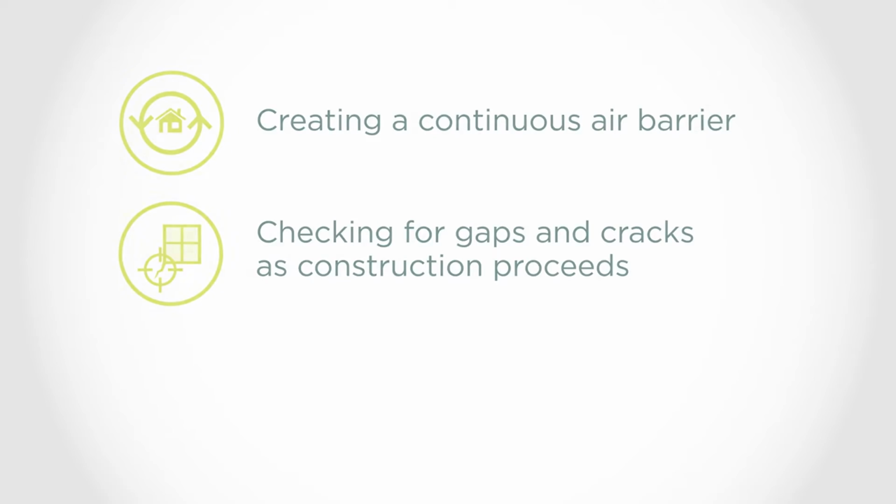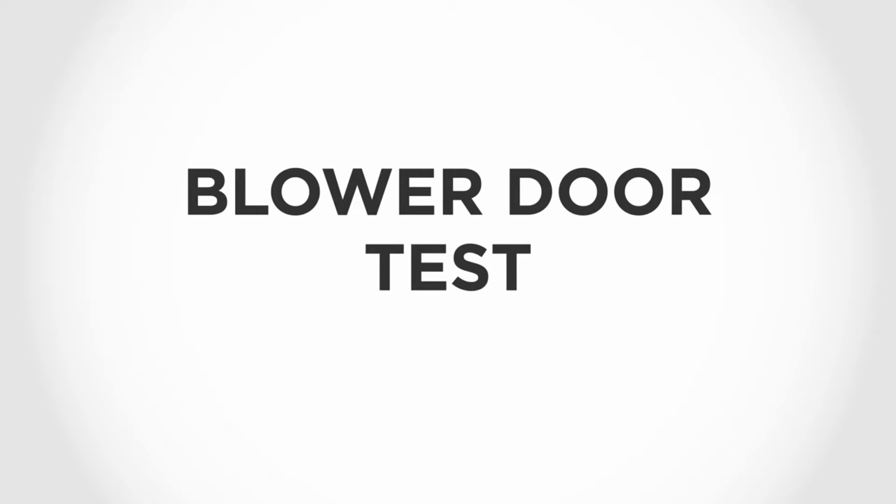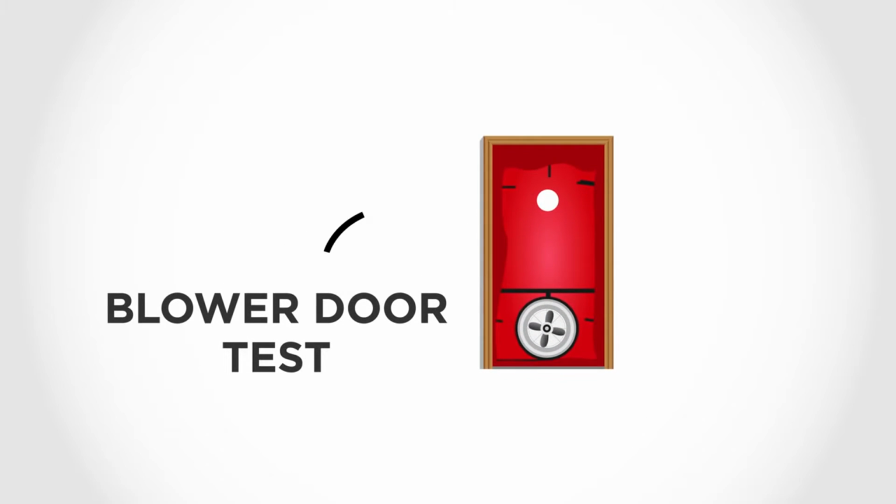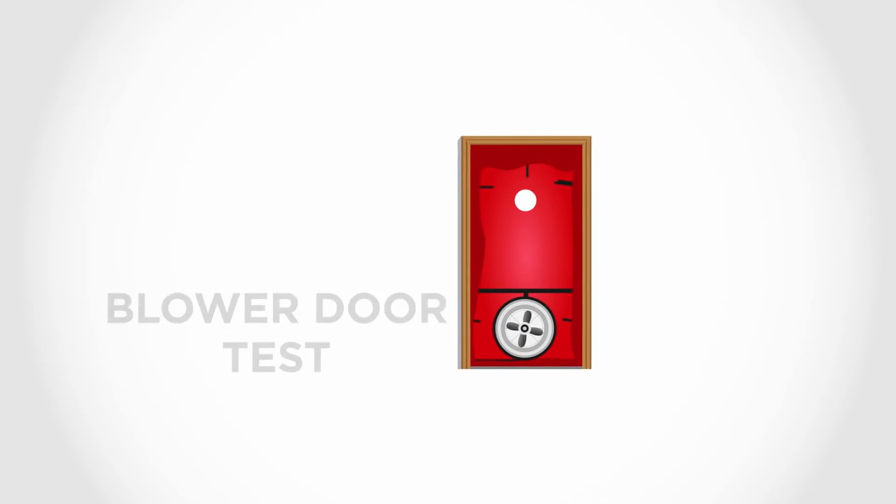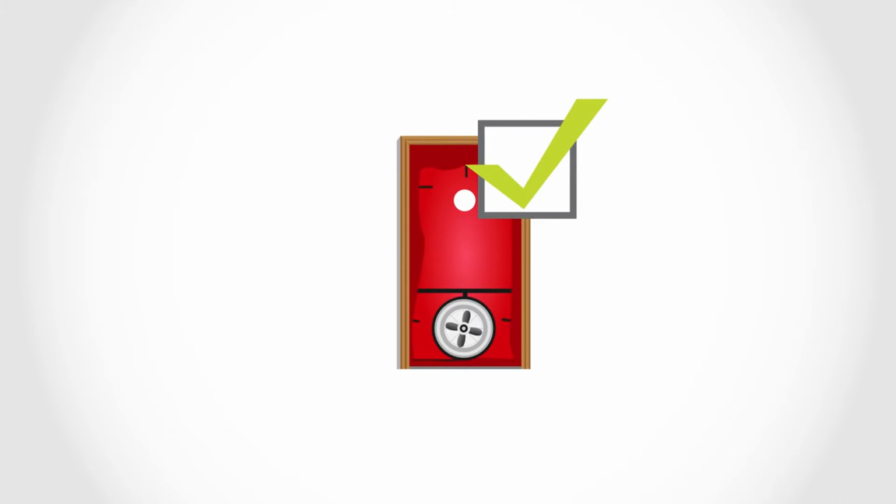Now let's discuss the blower door test. Once construction is complete, including all final envelope penetrations, it is time for the blower door test. Projects must use a blower door test to prove air tightness during final inspections. This is how it works.